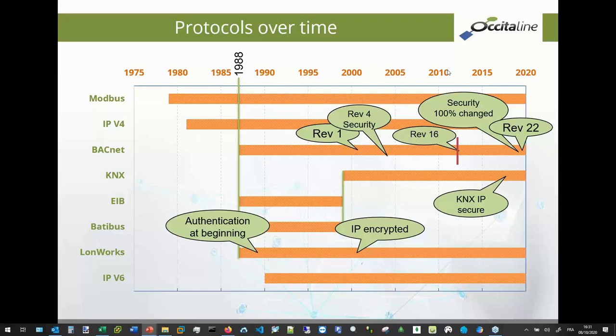Revision 1 is always version 1, starting in 1995 exactly, but they started very slowly, and they increased. And today, there is no device in the field certified after revision 16. It's very, very important, because you do not implement the new cybersecurity, sorry. They do not implement some mandatory objects, because it's necessary to modify everything in revision 17. And revision 16 has a date of 2012. It's very, very old, compared to 2020.